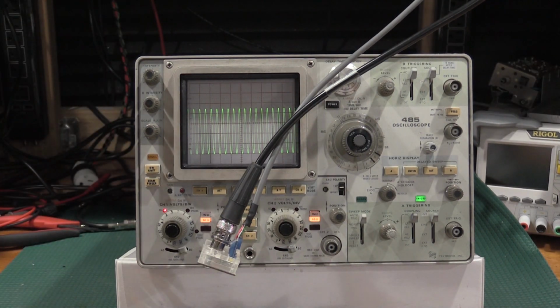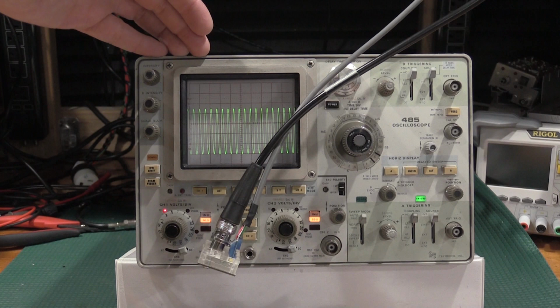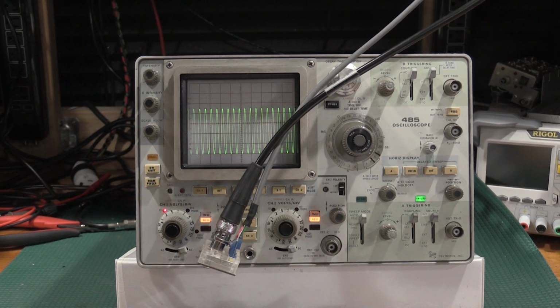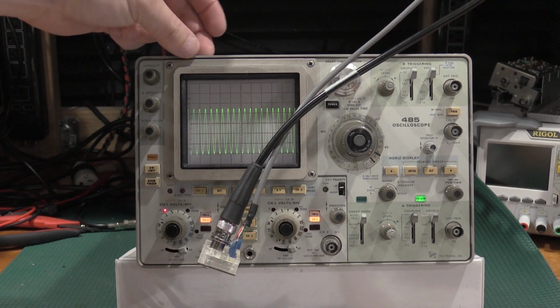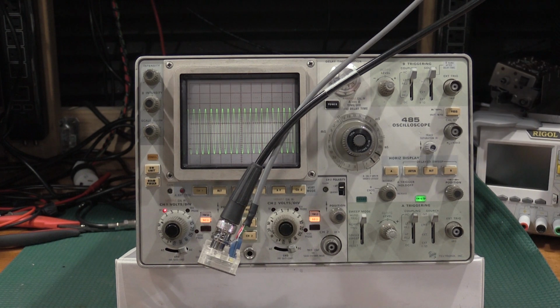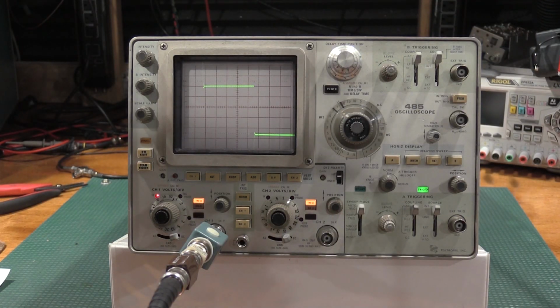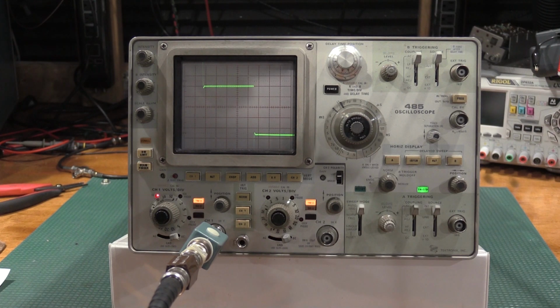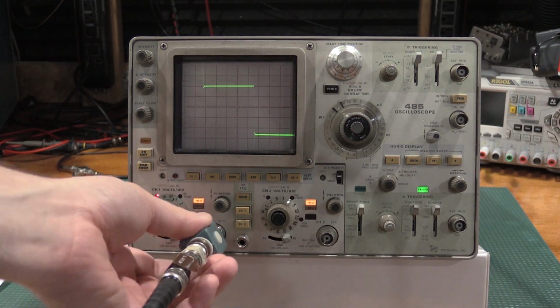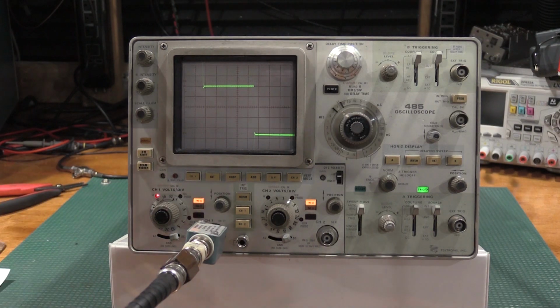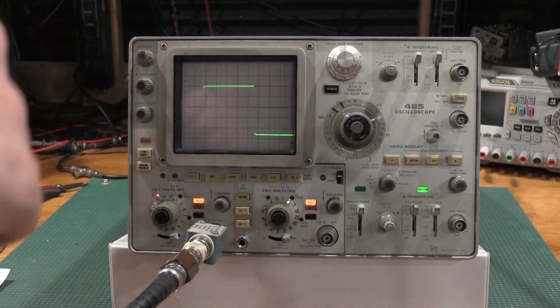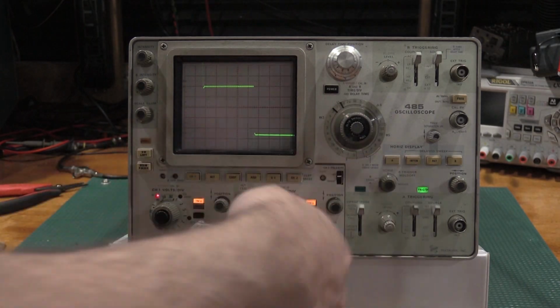Now, one thing to note on the 485, they only achieve the 350 megahertz bandwidth on the 50 ohms. The 1 meg input is a 200 megahertz bandwidth on these. So still very, very good for a portable scope, and still very useful. Okay, I'm getting set up for the 1 megohm calibration. I'm using an RC normalizer instead of a probe because I have them in the lab and I've got them available. So I'm checking. Channel 1 looks good. Move over to channel 2.